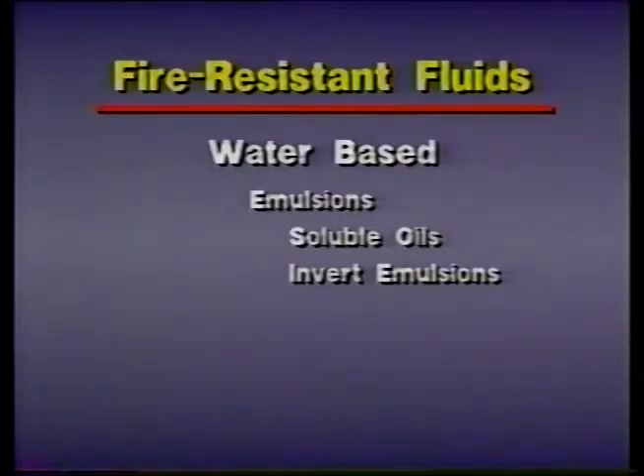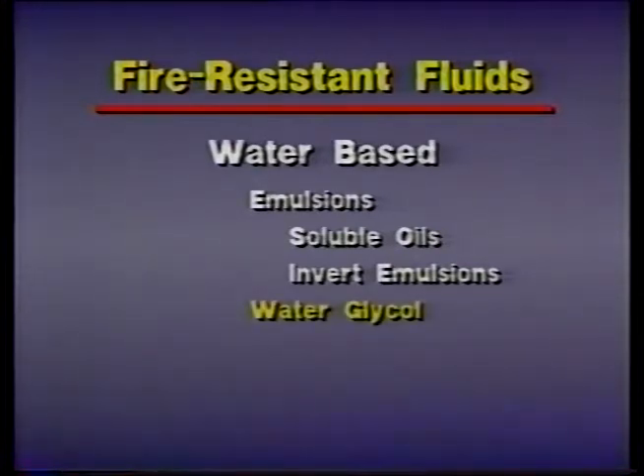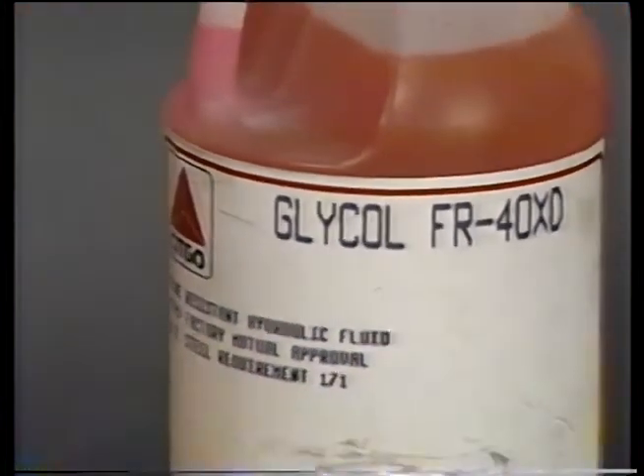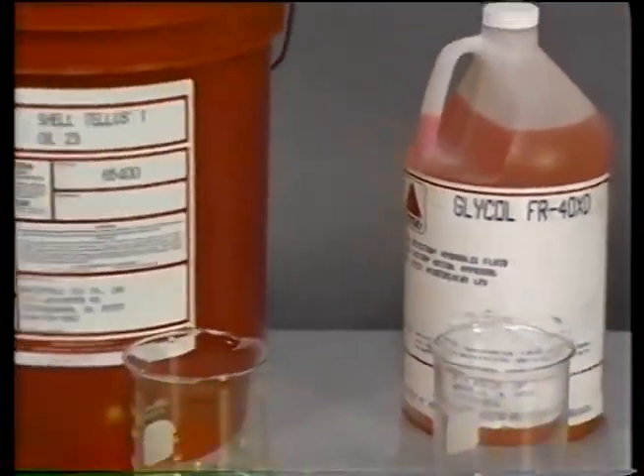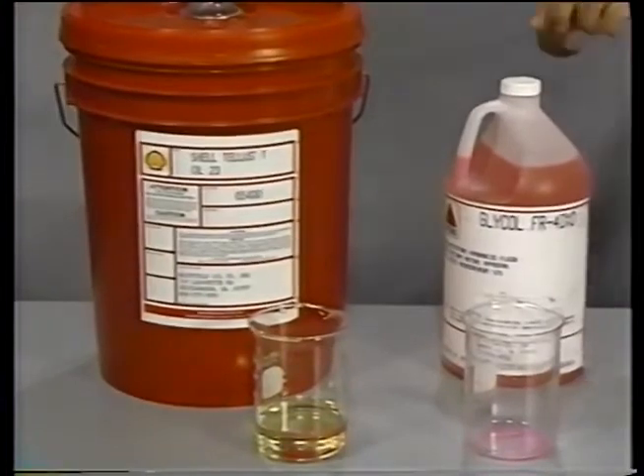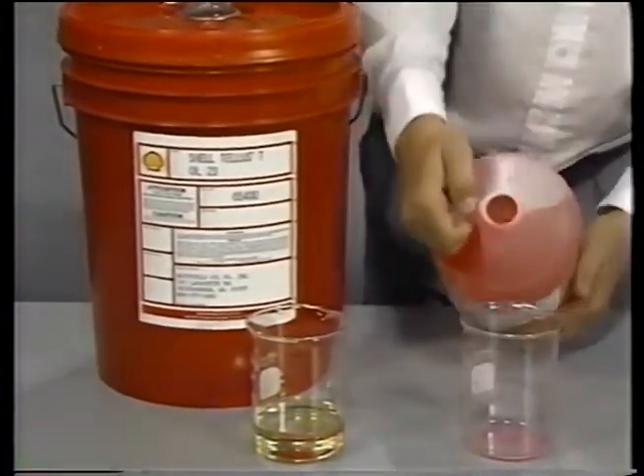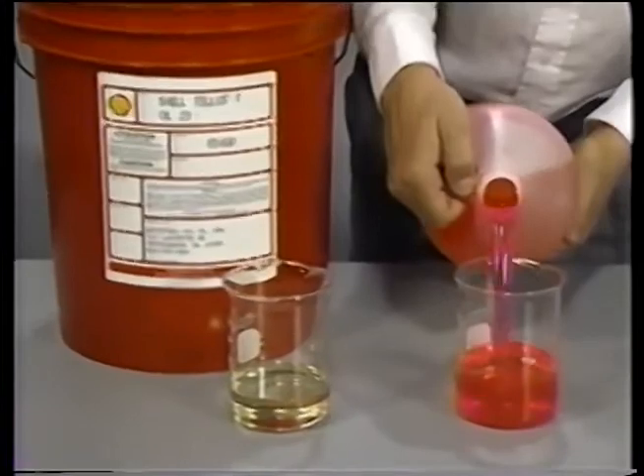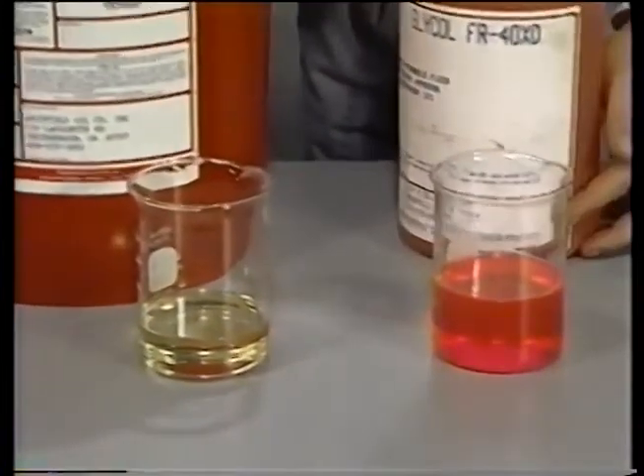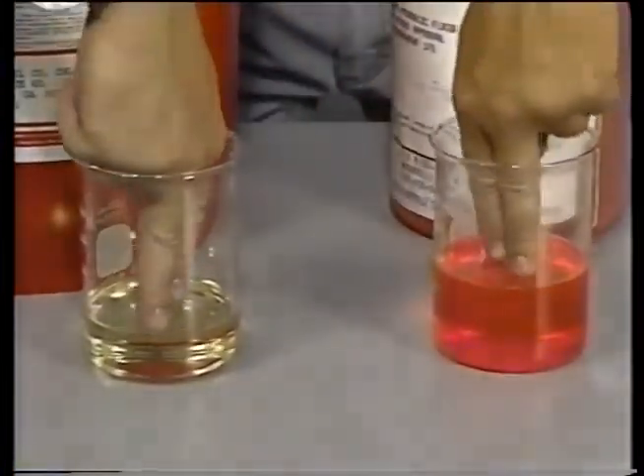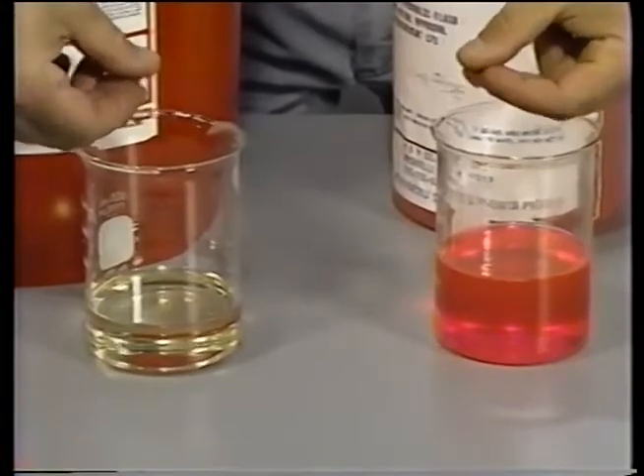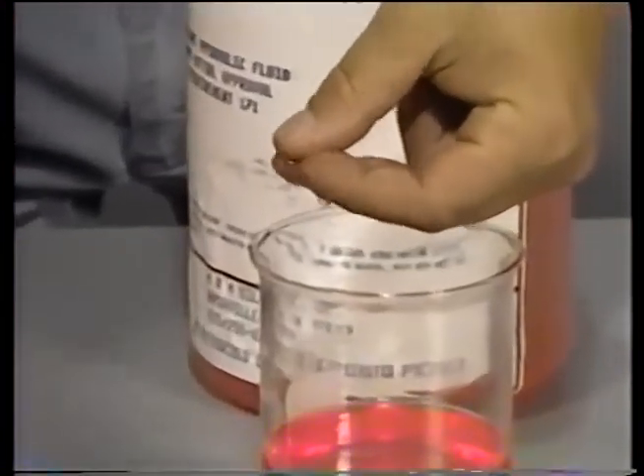Another type of water-based, fire-resistant fluid is water glycol. It's made from a mixture of about 40% water and 60% glycol, a chemical similar to automobile antifreeze. Water glycol fluids have some advantages over emulsions. They can be used at much lower temperatures without freezing or separating, and water glycol fluids are more fire resistant than emulsions. But water glycol fluids don't lubricate as well as petroleum oils and they tend to cost more.